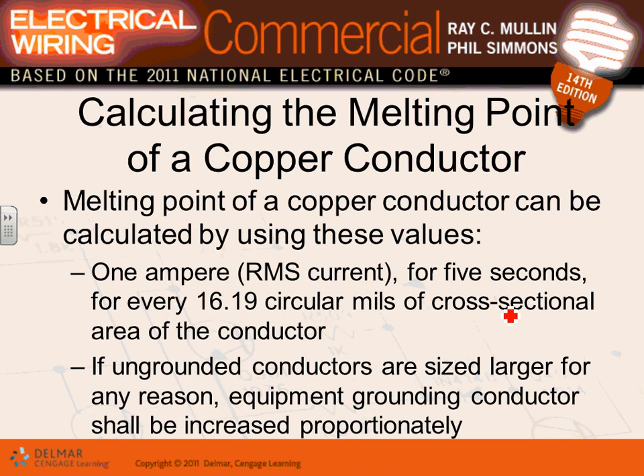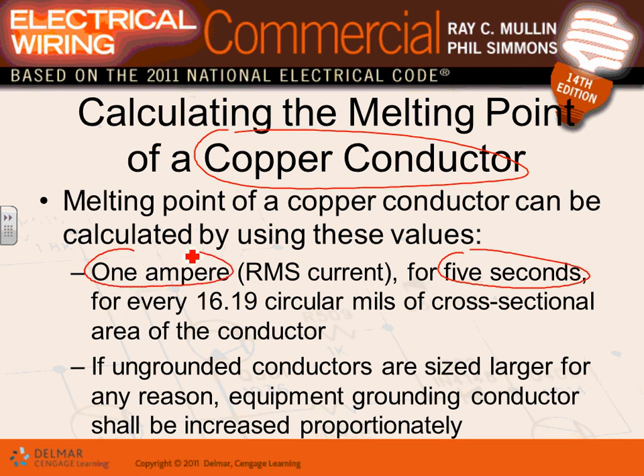When does the copper melt? Copper melting, guys, the value that they use for copper melting. Now we're getting to withstand. When you have a conductor, guys, you have two things: you have the insulation that's going to melt, and also you have the copper itself that's going to melt. So for the copper, the calculation they use is the same thing, that magic number, 1 amp for 5 seconds, for this circular mils, 16.19 circular mils.